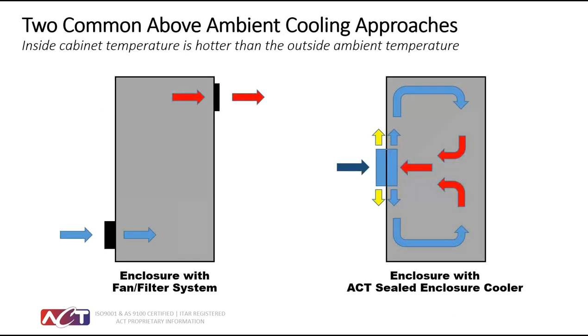So a very common way to cool an industrial control cabinet today is with fan filters, and those require two holes in the cabinet, like the application you see on the left. So essentially what you're doing is drawing in outside air or plant air that could have hydrogen sulfide gas, it could have chlorine, it could have high levels of dust or contaminants. You're drawing that in and over all of your control systems. If it's a real humid environment, you're making the internals of your cabinet wet and damp. And then as you go through the day, if the temperature starts to go down, you could get condensation inside of that enclosure.